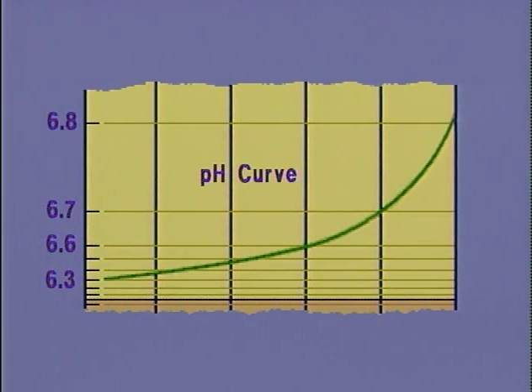Between pH values of 6.3 and 6.6, the curve is fairly straight and flat. Between the pH values of 6.6 and 6.7, however, the curve begins to rise more steeply, and it continues to rise steeply up to pH 6.8. Because this graph does not follow a straight line, neutralizing pH is a non-linear process.